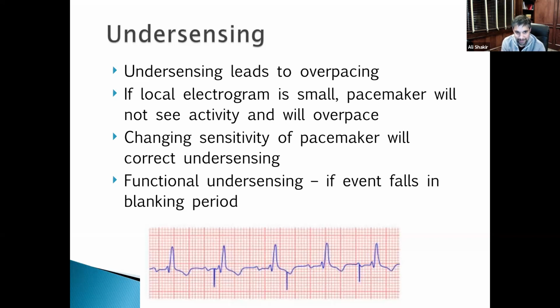One more concept. If the event falls in a blanking period, and we talked about the blanking period where the device's eyes are closed and not looking, it's an example of functional undersensing, right? So if you extend the blanking period for some reason and activity happens there, that'll be functional undersensing. On the other hand, if the event happens in the refractory period, the device sees the event but doesn't act upon it. And in the blanking period, the device doesn't even see the event.